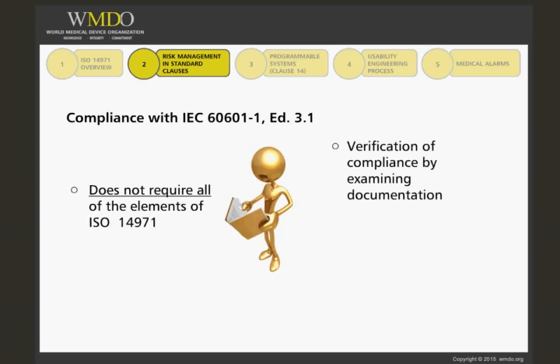The verification of compliance with the risk management requirements, as outlined in ISO 14971, is achieved by examining the manufacturer's documentation required by that standard and an assessment of the processes cited in the standard. In practice, a manufacturer must provide all related quality system policies, procedures, work instructions, and forms for review by an inspector, who can then determine whether they cover all elements of ISO 14971 required by the IEC 60601-1 standard. So instead of conducting a traditional audit, a document review is conducted to verify that the requirements have been met.